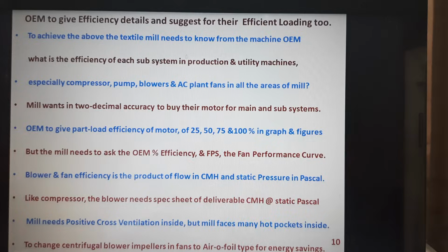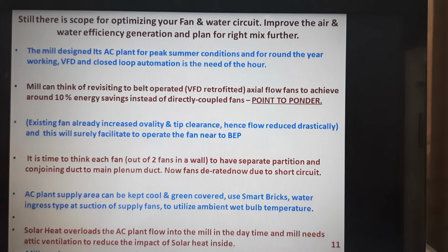Still there is scope for optimizing your fan and water circuit, which improves the air and water efficiency at the generation and at the right mix later. All the mills are designed, the AC plant is designed for the peak summer condition, and the VFD becomes mandatory for the AC plant.